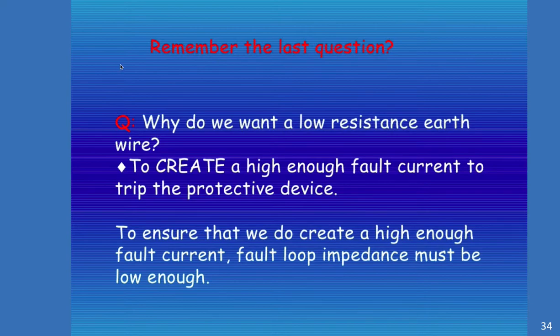Got to remember what the last question is. Why do we want a low resistance earth wire? Or actually why do we want a low fault loop? And the answer is to create a high enough fault current to trip the protective device.